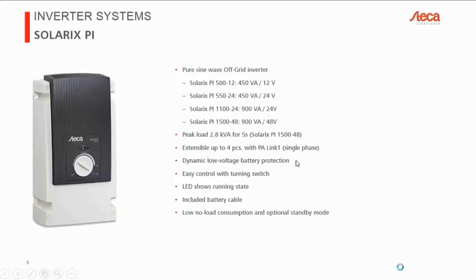We have a dynamic low-voltage battery protection. So there's a limit for when the unit turns off. I believe it's 10.5 or 11 volts as the absolute minimum. And then depending on how much load is applied, this is varied. So of course, if you have a big load on your inverter, then the battery voltage will be lower than even if you have exactly the same state of charge than if you have a small load, simply because of the internal resistance of the battery. So this device will dynamically compensate for that by changing the shutoff value for the low voltage disconnection.